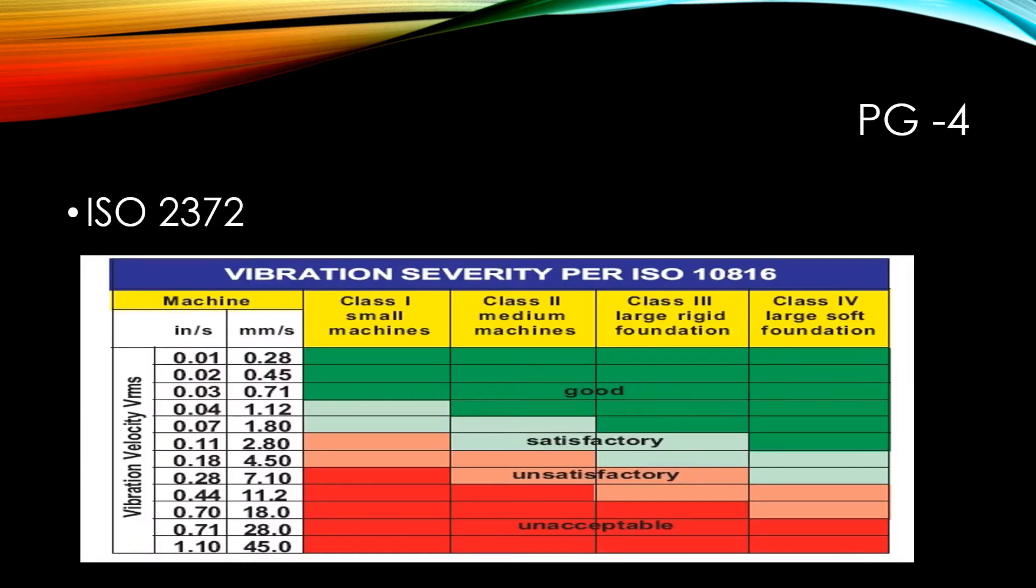So the next question is which ISO standard should we follow to find out the vibration severity of the machinery? Here we are using ISO 2372 that is BS 4675. The machinery is classified into four classes: class 1 for small machines, class 2 for medium machines, class 3 for large rigid foundation, class 4 for large soft foundation. We can refer this table while taking the vibrations.